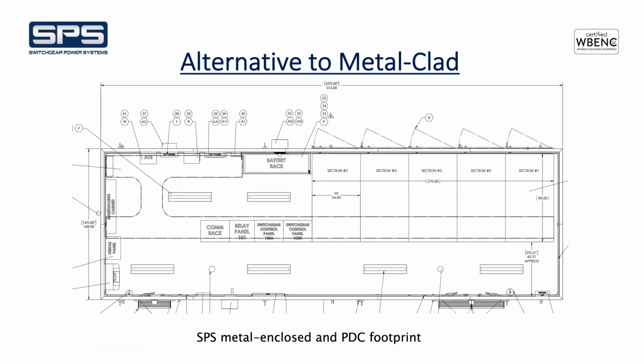So the switchgear does get a little bit wider, and that is driven by the switches being incorporated with the breaker. But the depth of the switchgear went from 11 feet down to just over 8 feet. So that in and of itself would have reduced the width of the E-house from 21 to 18 feet. But they got the added benefit of reducing the walk-in aisle width, which brought the total width down to 14 feet. And so we shipped this building to site in one piece.